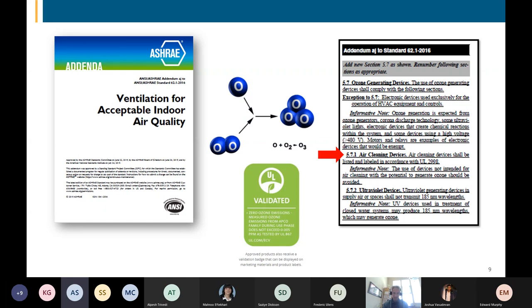If you want to comply with the ASHRAE standard, and if you want to comply with recommendations from the Centers for Disease Control and Prevention, the CDC, here in the United States. Underwriters Laboratory is an agency here in the U.S. that will validate and test manufacturers' products. A manufacturer sends their electronic air cleaning technology to UL. They put it in an ozone test chamber. They put an ozone testing device 2 inches off the emitters of whatever the device might be, the electronic components of the device. They turn it on, they run it for 24 hours.